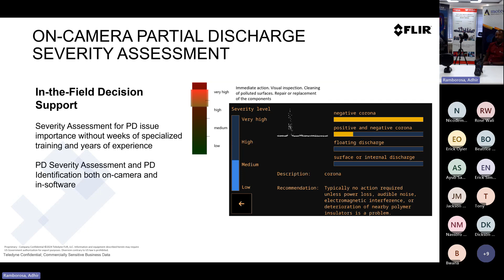If you look at the little explanation or recommendation on the screen, it says typically there's no action required unless there is actual power loss, I beg your pardon. However, from a severity perspective, if it starts to look at things like tracking and arcing, and it classifies it, it's going to pick up that severity level and tell you, listen, this is now a high potential problem. Please, can you have a look at it, and it will give you some form of recommendation. Does that answer your question? That answers the question. That means the unit with its advanced AI addition helps to classify the kind of partial discharge. It definitely does. It definitely helps with the classification process.